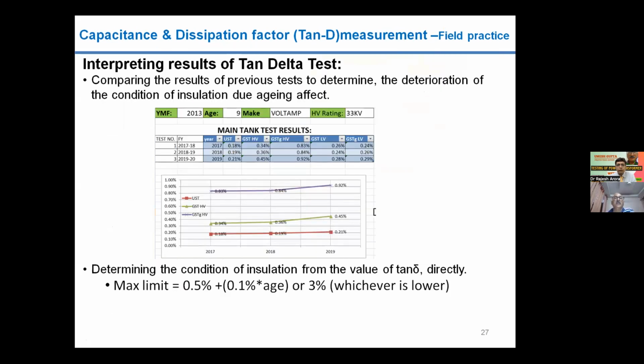Next, these are the curves we are showing here for different transformers, and the trends. Trends are used, as I mentioned earlier, to know what the issues are, or whether contamination or moisture ingress is taking place. So it is very important to see how the trends behave when we measure tan delta over the years. In this picture, we are showing 2017 to 2019. Many times we even compare 5-year trends. So what are the variations?